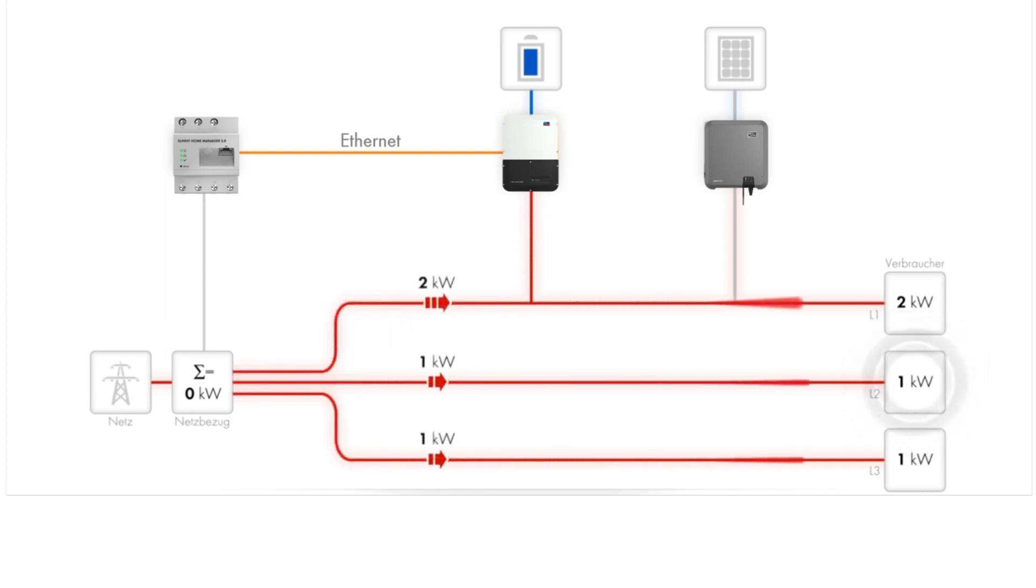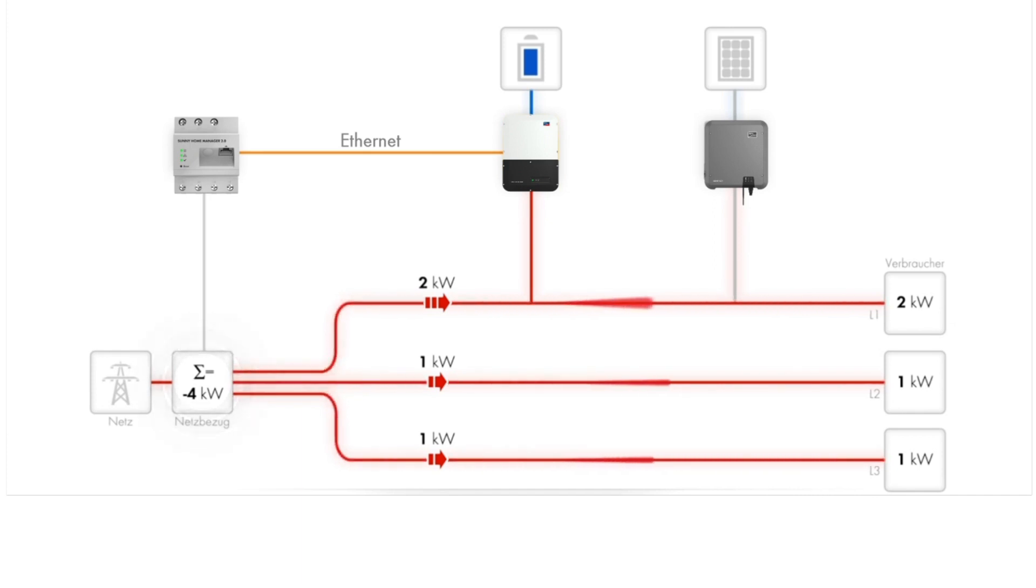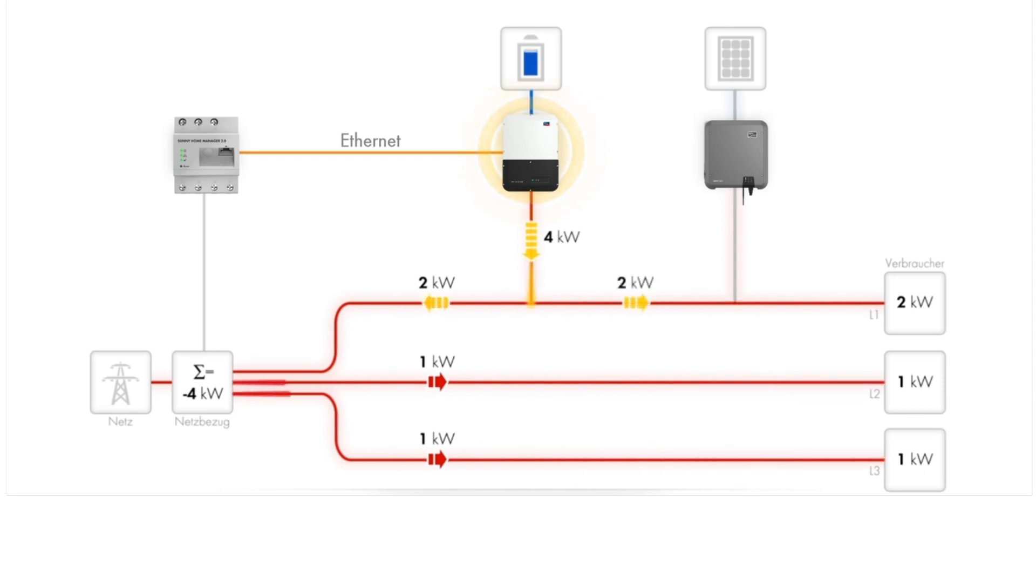Now there is four kilowatts imported at the grid connection point. In reaction to this, the Sunnyboy storage and Sunnyhome manager will then discharge the battery at a rate of four kilowatts to compensate.